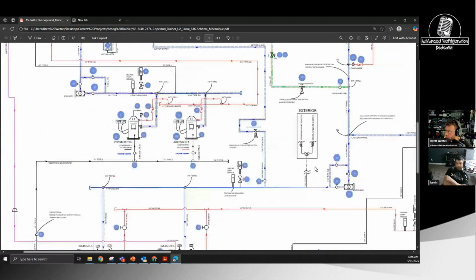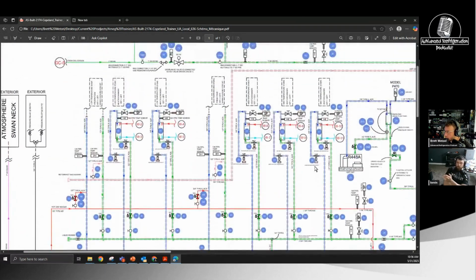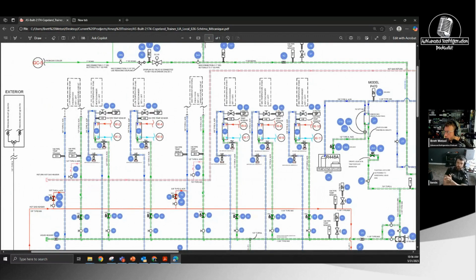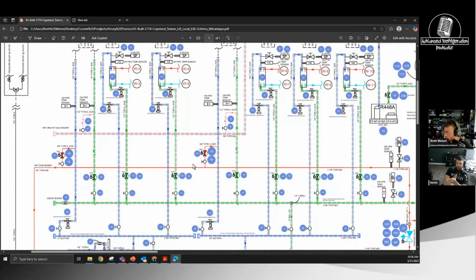I'll go back to the circuit. So we just had liquid line solenoids on here, and normally you wouldn't have that for the most part, but this is a trainer, and if the compressor shut down, it needs to instantly shut off. And then we have EPRs, and we have liquid stepper valves for the suction superheat.